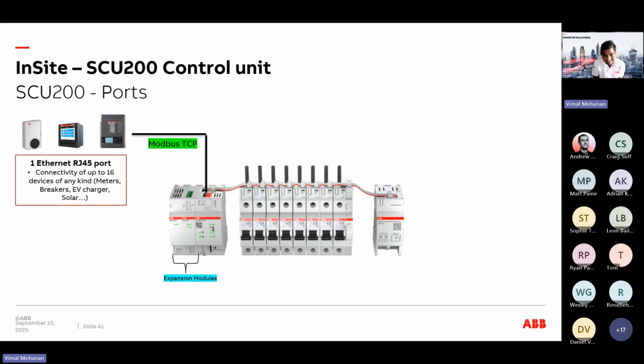You can connect up to 16 Modbus TCP devices. So bear in mind, we're not just talking about meters. It could be EV chargers, it could be solar. As long as they communicate on Modbus TCP, 16 of them can be done.